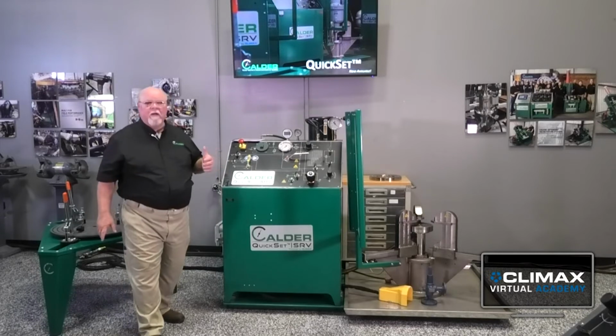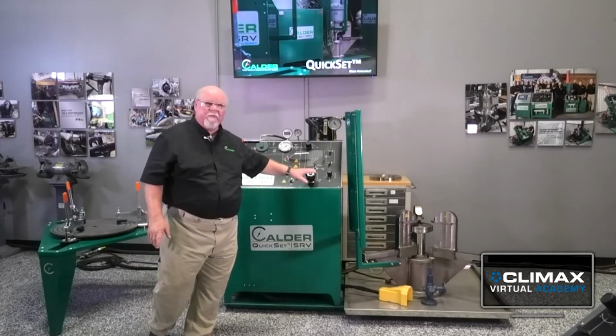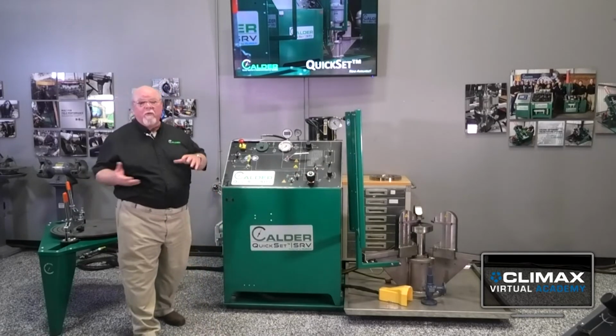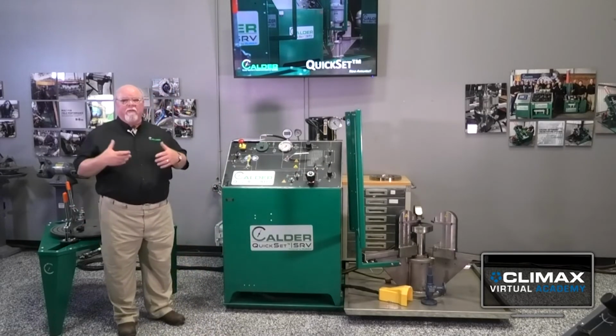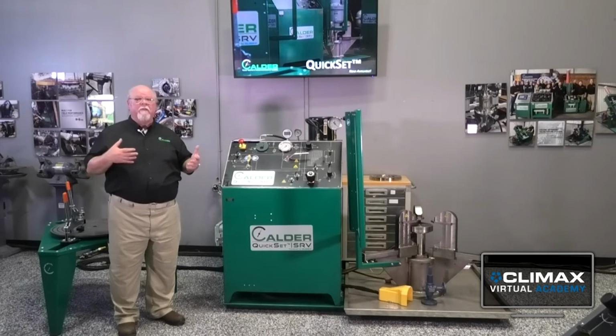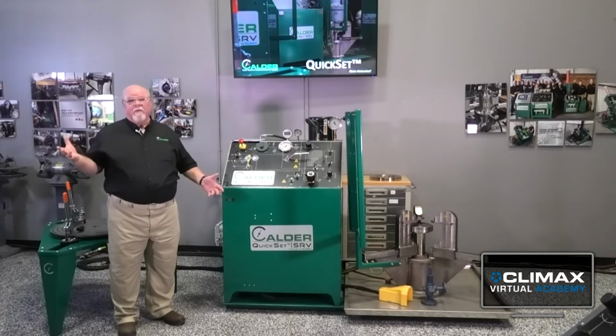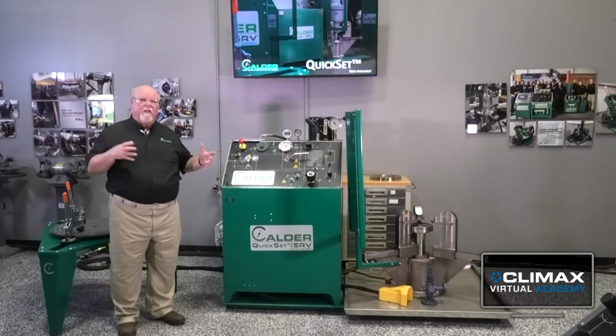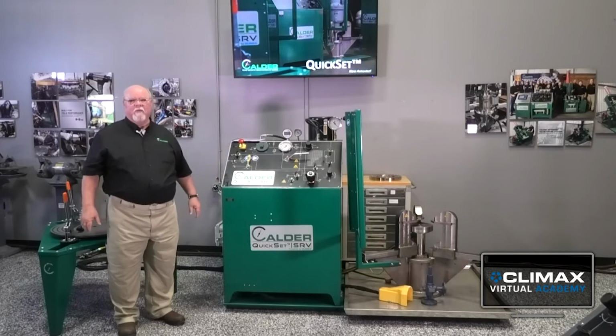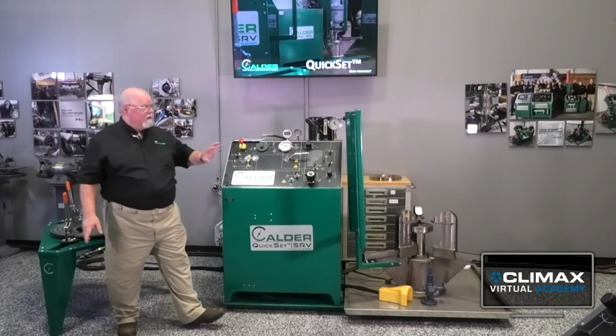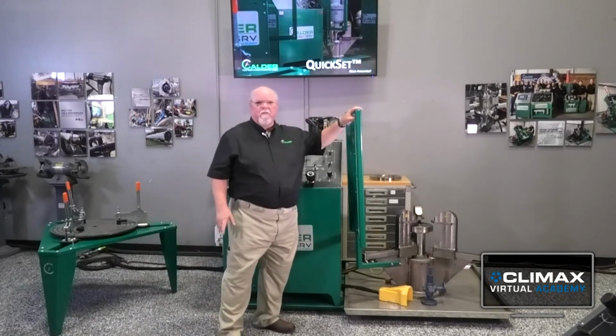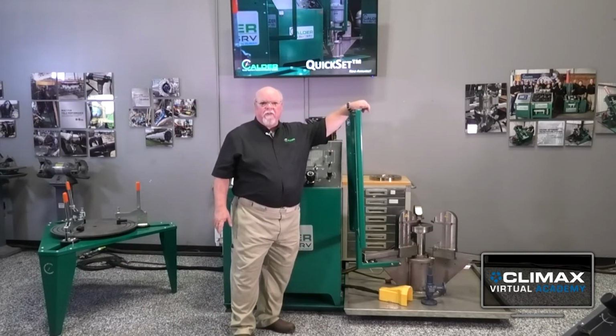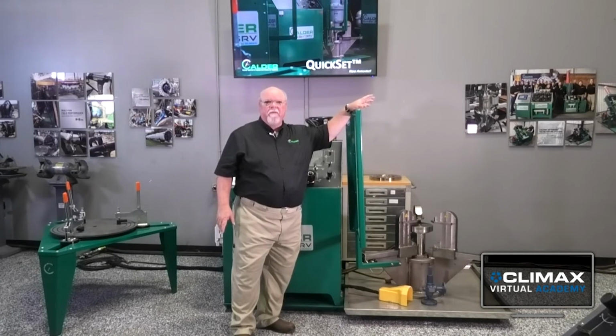For threaded inlet valves, the test plate itself is set up for flange valves. So if you have a lot of portable or threaded inlet valves, we sell a series of MPT adapters. They're MPT male and female, all in one adapter plate, with an adapter threaded from 1/2 inch up to 2 inch. That's a pretty easy combination that goes to the field as well. And the last is, as standard comes the splash shield here, but we also have a safety enclosure that can go 360 surround of the test port.